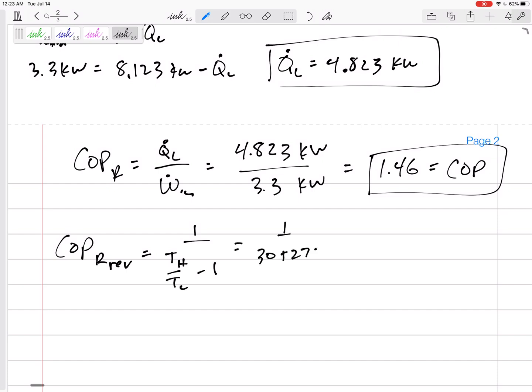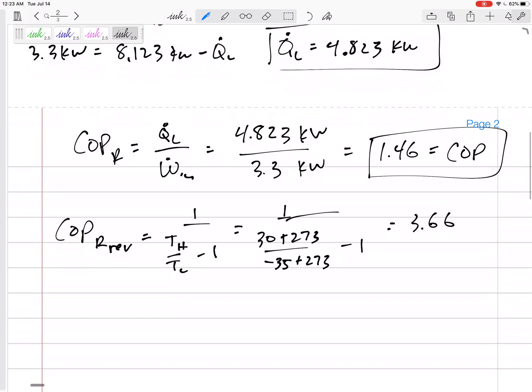1 over TH is 30 plus 273, negative 35 plus 273, minus 1. The best possible coefficient of performance: 3.66. You see, compared to the 1.46 that we actually have. And I know that COP is also equal to QL over...